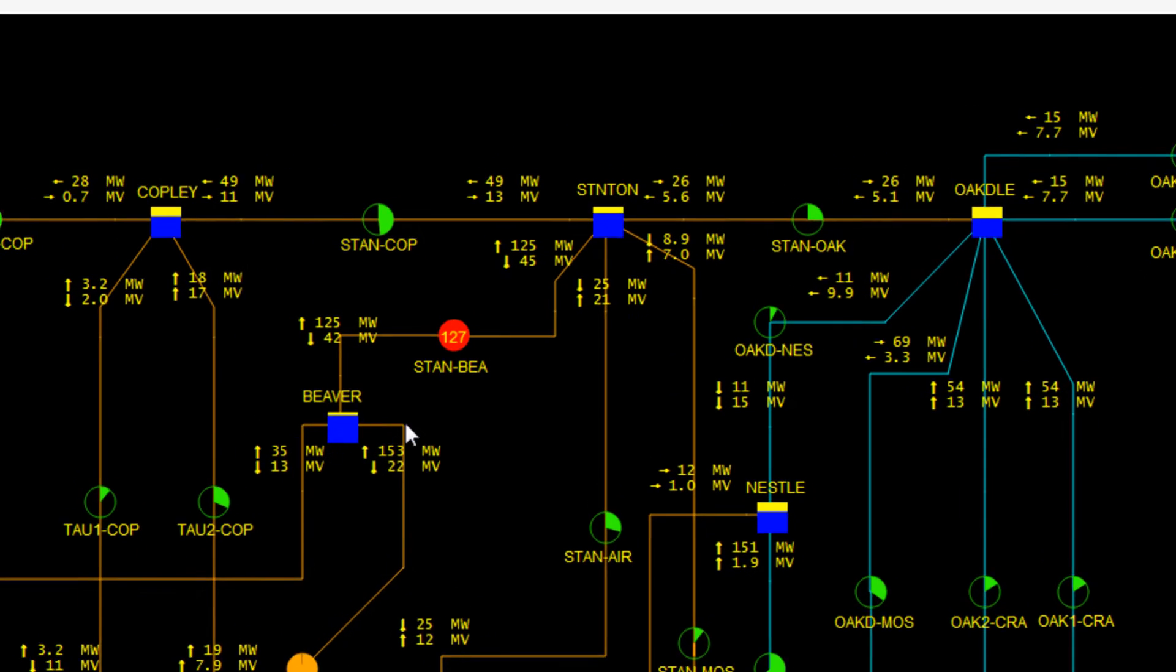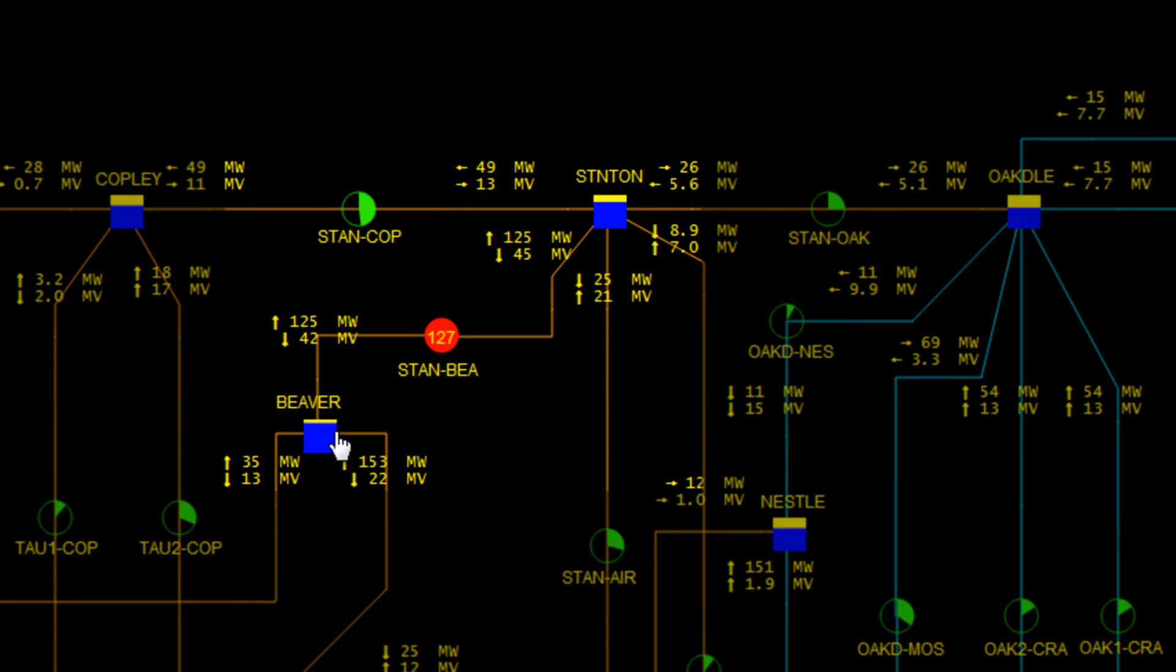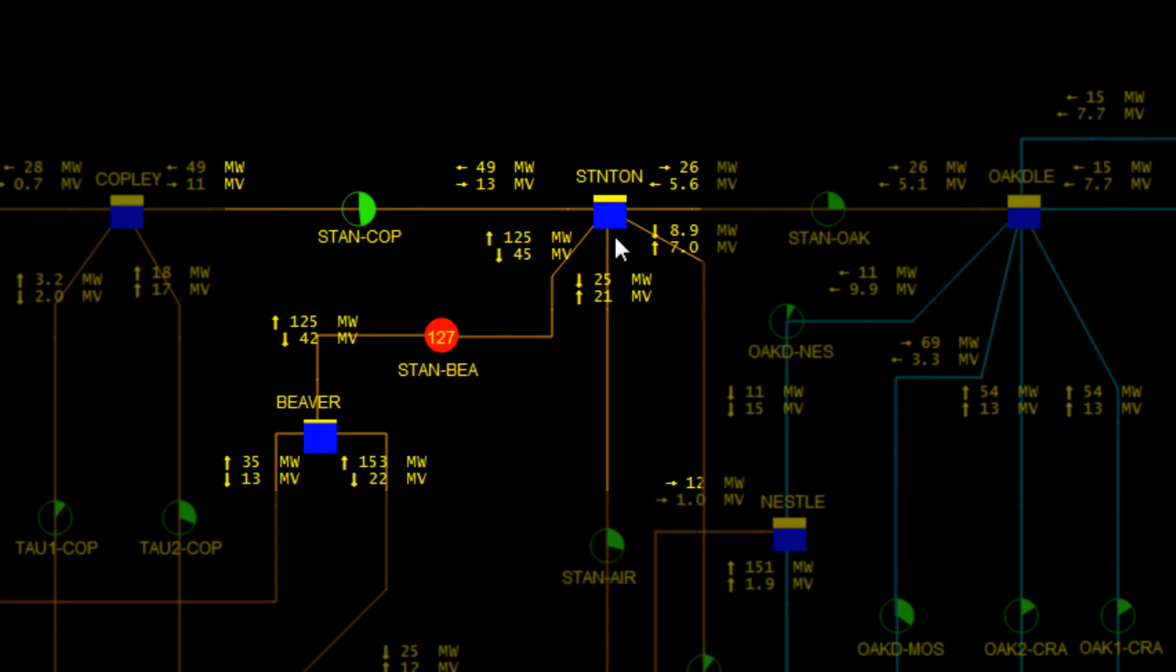We notice the direction of the flow on the overloaded line is from Beaver to Stanton. To relieve the overloaded line, we need to reduce generation on the sending end and increase generation on the receiving end.